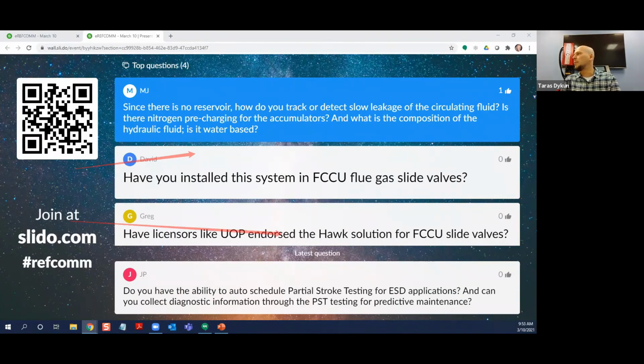So basically, at that point in time, you would probably see the level indicator. There is a level indicator inside this little red box, and we can install one outside for you, in a little additional reservoir, which will show you the amount of fluid within the unit. And at that point in time, you'll be able to see if there is any leakage externally. However, internally, you would see the operation of the actuator start faulting out, or you would not be able to position the valve as well as it should, because it would start trying to catch the position or trying to position the valve.